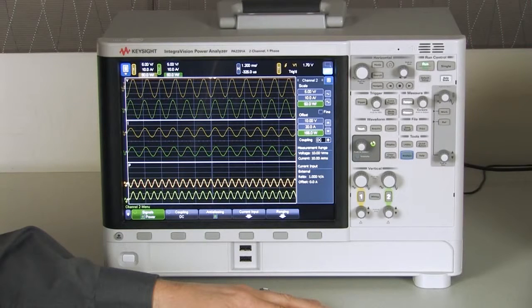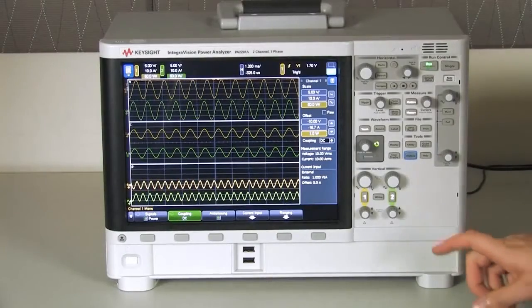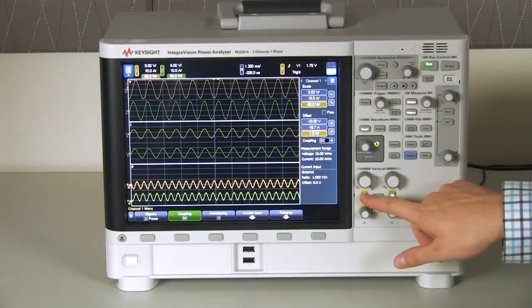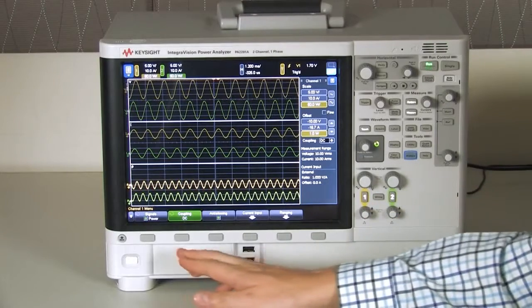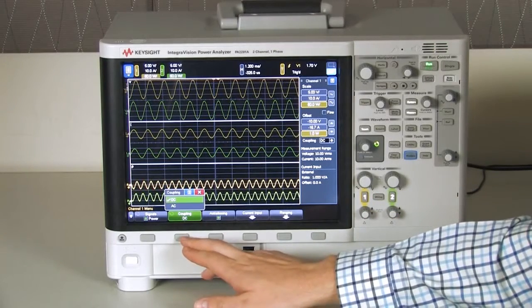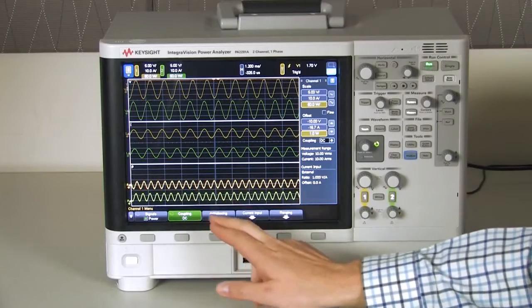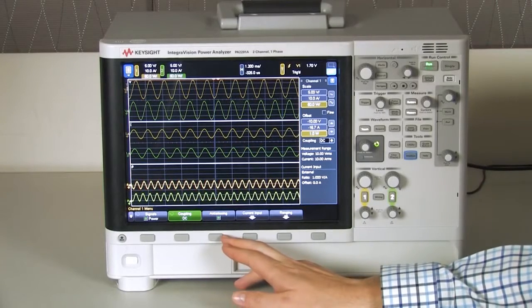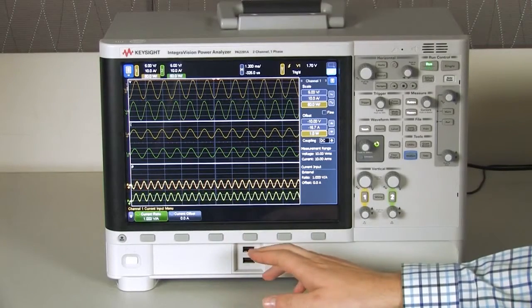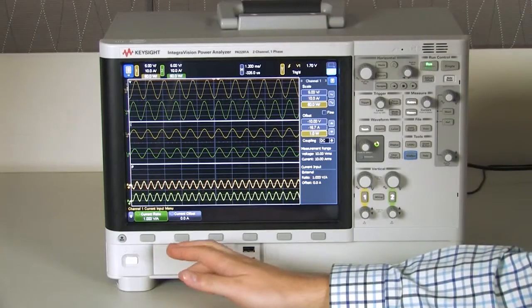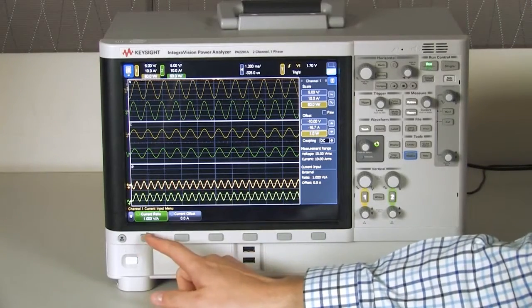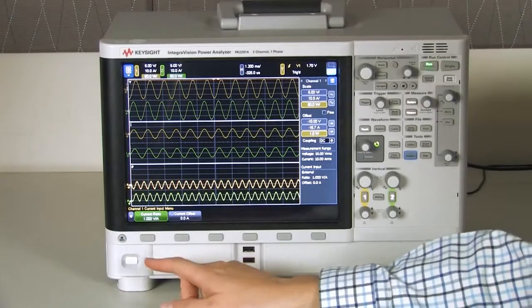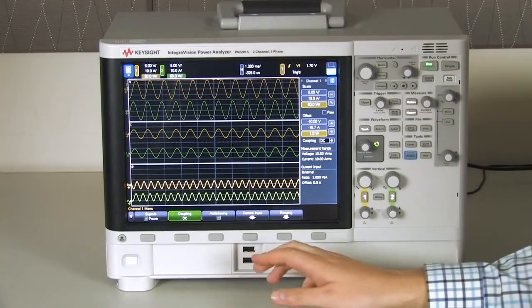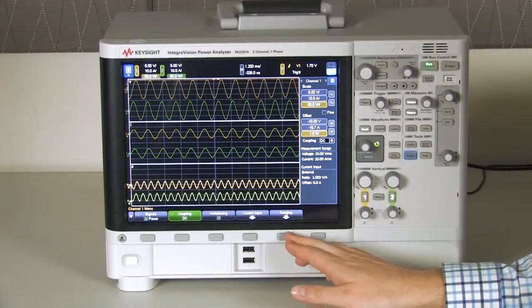Now Blake is going to show us the setup of the power channels. So here's an overview of the channel menus. If we go into channel 1, we can change the coupling to be either AC or DC, enable or disable anti-aliasing, and control the current inputs. If we have a current probe hooked up, we can set the ratio and offset for our probe.